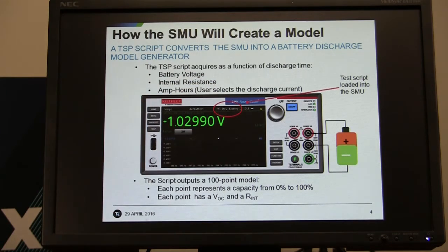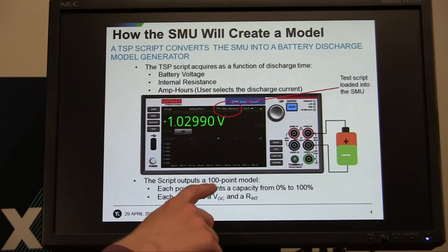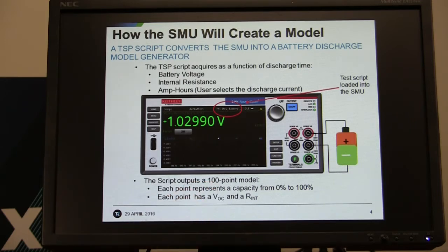When it's done discharging the battery, it's going to produce a 100 point model that can then be loaded back into the 2281S battery simulator to be used to simulate a battery.